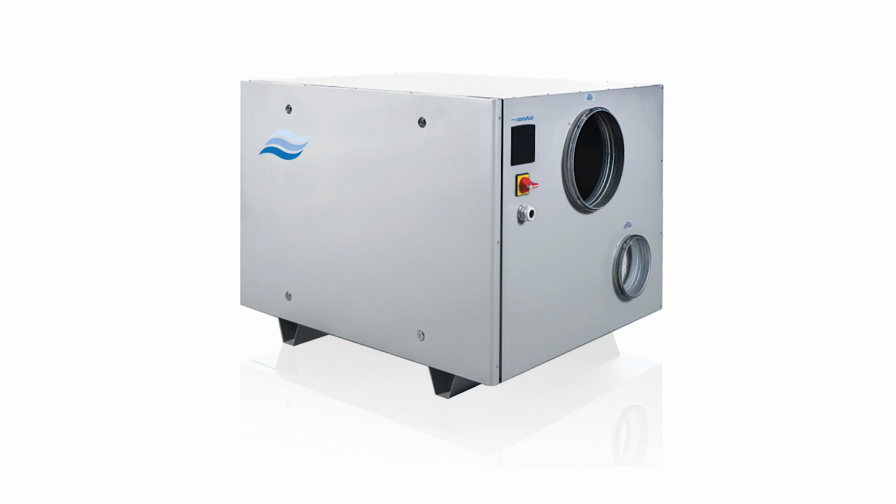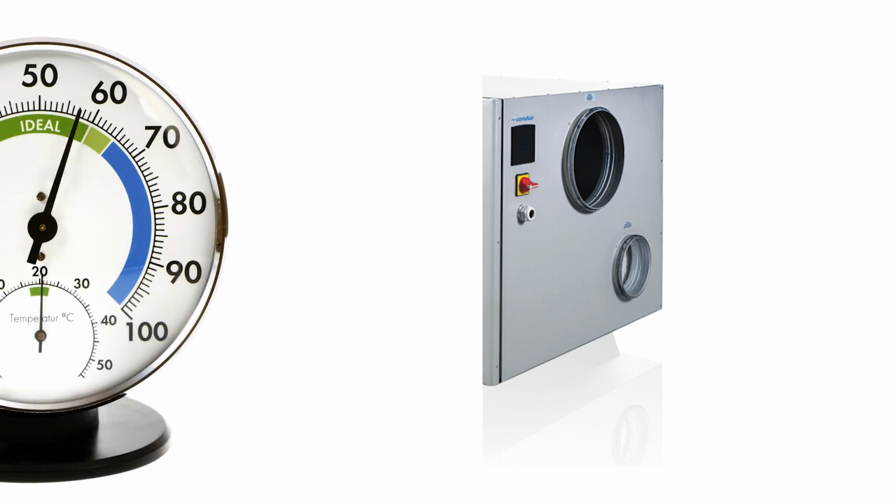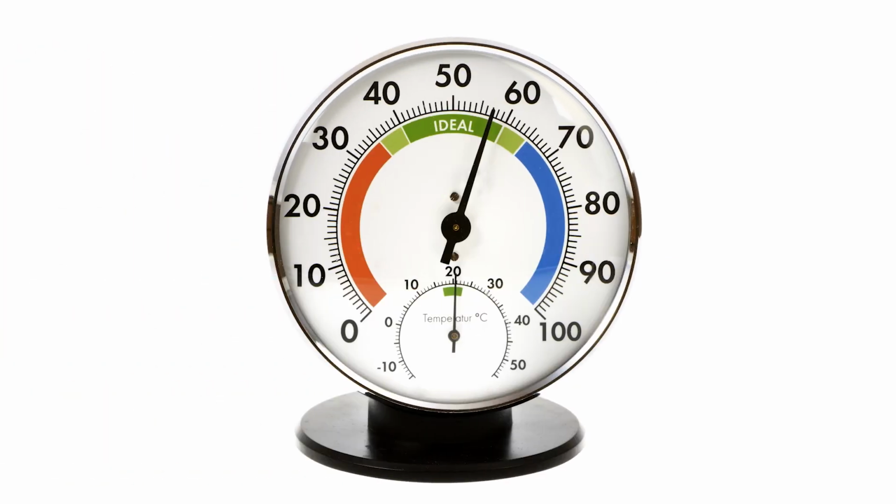So apart from the ambient temperature and heat gain, what should be considered next? Well, the next question is to ask what humidity level is needed in the area and how much variation is acceptable. Environments such as clothes drying rooms or swimming pools don't need extremely dry conditions. Simply maintaining a mid-range humidity of around 50 to 60% RH is enough to stop condensation or mould forming in these areas and meet the client's needs.